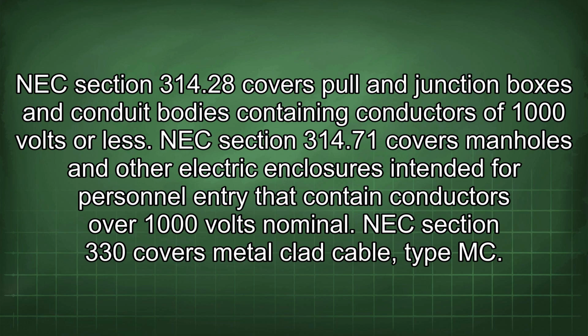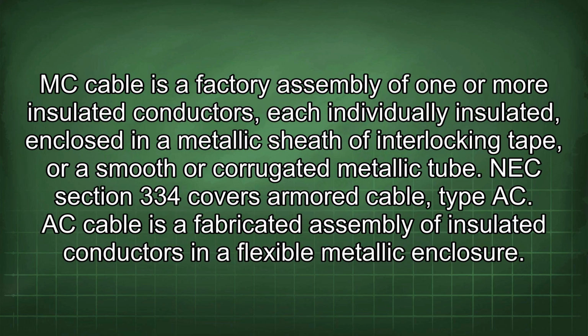NEC Section 330 covers metal clad cable, type MC. MC cable is a factory assembly of one or more insulated conductors, each individually insulated, enclosed in a metallic sheath of interlocking tape, or a smooth or corrugated metallic tube. NEC Section 334 covers armored cable, type AC. AC cable is a fabricated assembly of insulated conductors in a flexible metallic enclosure.